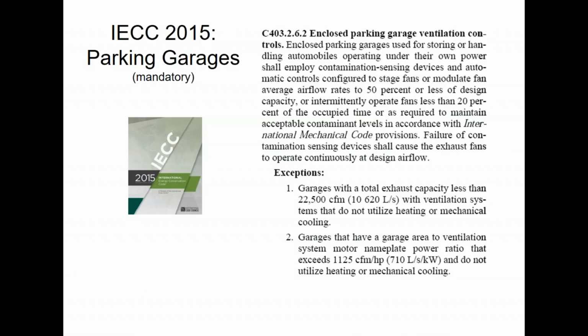Parking garages. There are some control requirements there as well. For parking garages, we'd be using CO sensors instead of CO2 like we use for people. Right? CO, carbon monoxide, byproduct of vehicles. CO2, carbon dioxide, byproduct of people. We would need to use sensors like that in the parking garage per the energy code to throttle back the ventilation rates when there are no or fewer vehicles in the space. So keep that in mind.